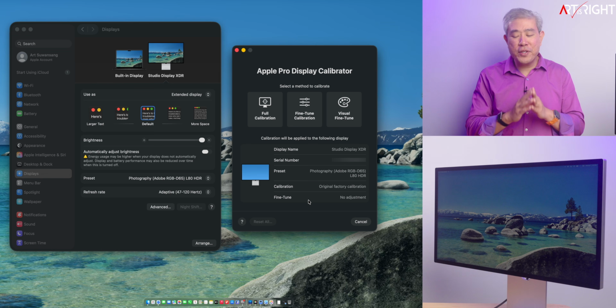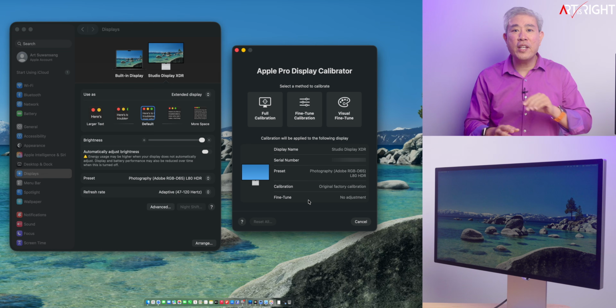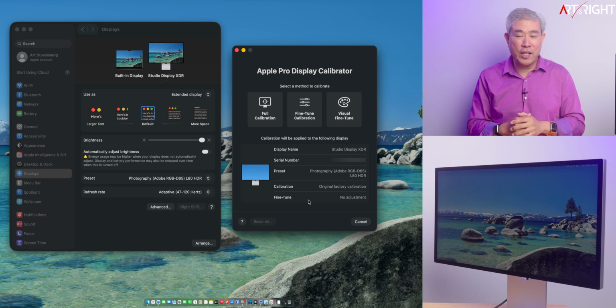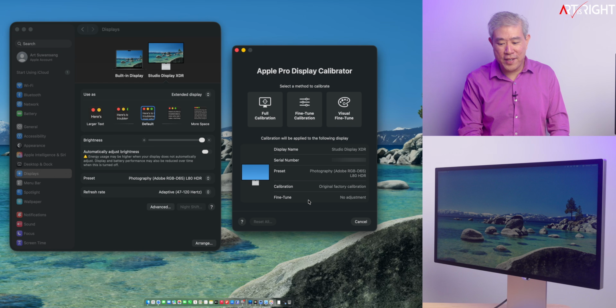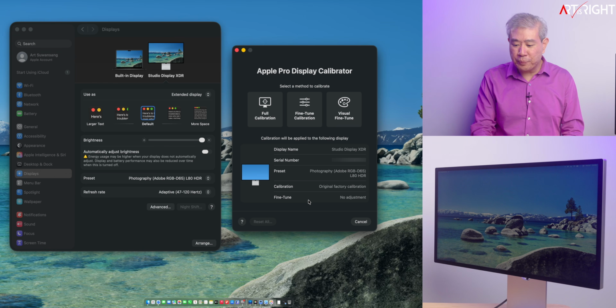The other thing to note is that once you do the full calibration, it removes all your fine-tune calibrations, so you have to go back and redo that. This is why I'm telling you not to do a full calibration all the time. I'd simply do this every 3, 6, 9 months, or a year, so your display has time to drift a bit before you redo everything.